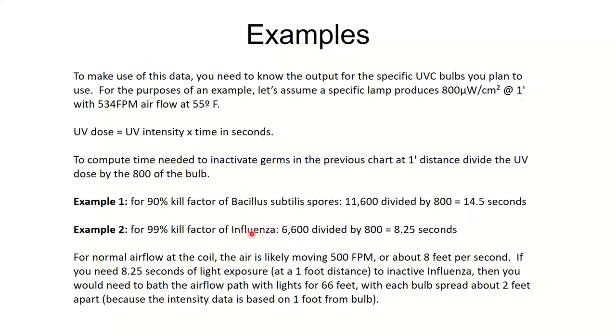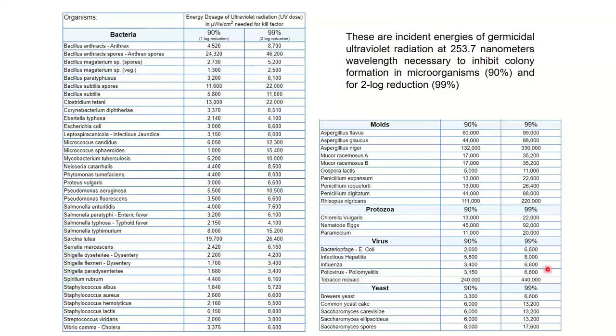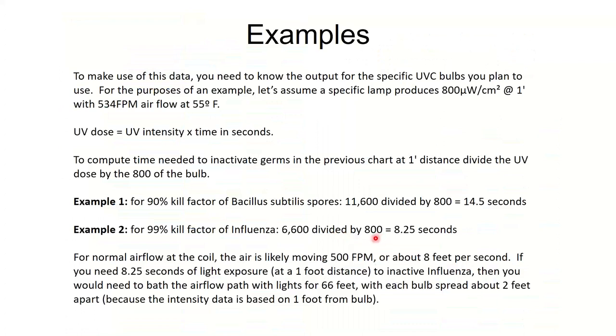If I take something else, let's say influenza, and I want to kill 99% of it, I pull that out of the table. Influenza, 99%, I need 6,600 divided by 800 for the bulb intensity that I have. I need 8 seconds of shine time within 1 foot to kill it. If I'm going to put this in my air handler coil, which is where these bulbs always go, my velocity is around 500 feet per minute because I'm limited, or I'll have coil blow off of the water. So that equates to about 8 feet per second. So for me to get 8 seconds of shine time at 1 foot distance, I'm going to have to put lights down 66 feet of duct and space them about 2 feet apart. That's going to be a lot of lights. Probably not going to want to do that, but that's what I'd have to do to kill this guy on one pass.